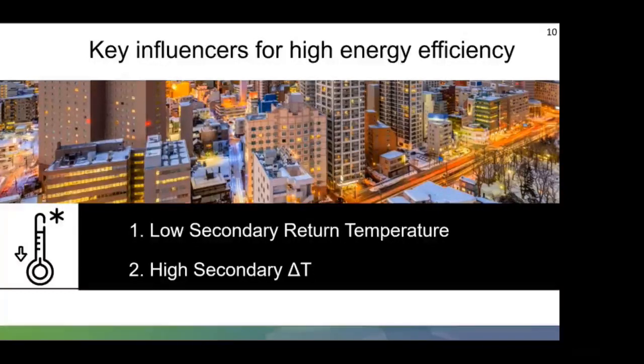Key influence for high energy efficiency. A key influence on the primary return temperature is the secondary side return temperature. The better we make the delta T on the secondary side, the better the primary becomes. By controlling the secondary side pumps through the substation as a package, the pumps become a pivotal part in aiding the maintenance of the return temperatures on the primary and secondary side. So again, low secondary return temperatures, high secondary delta T.